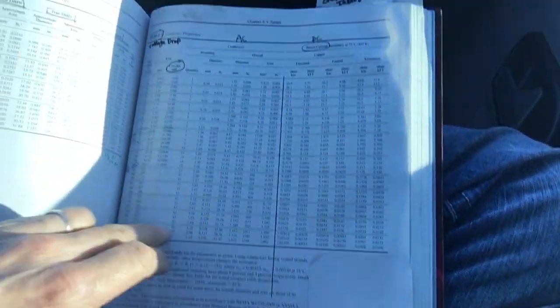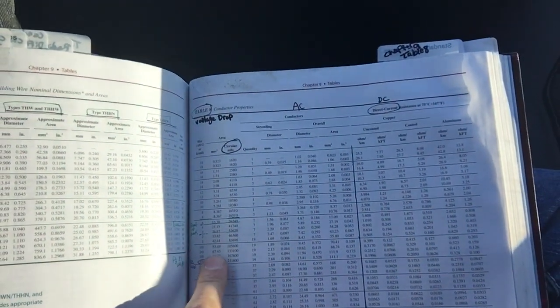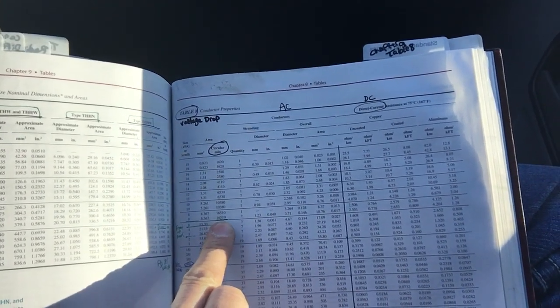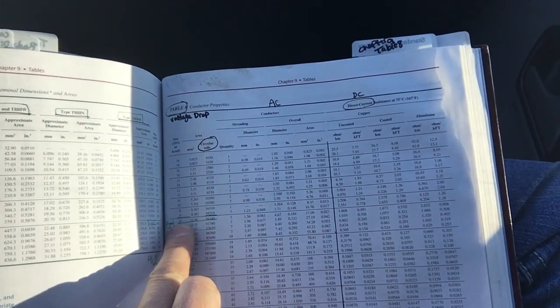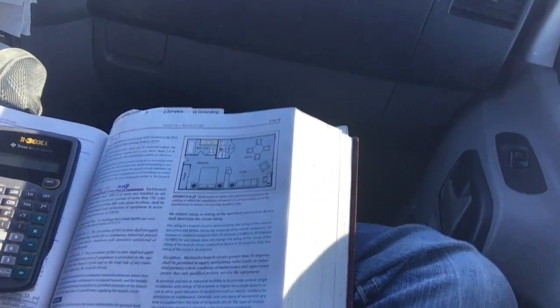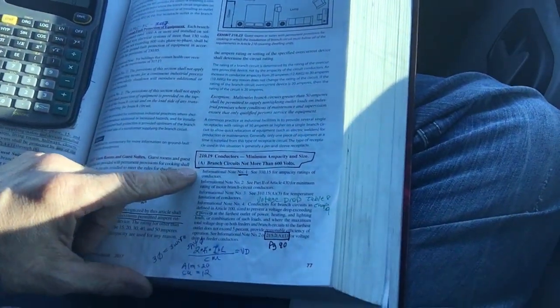It's going to show you here Chapter 9, Table 8, page 115. An 8 gauge wire has a circular mill of 16,510, and 6 gauge wire is 26,240 — those are the numbers I want to focus on. You'll find your voltage calculation in 210.19, which talks about minimum ampacity size of branch circuits.